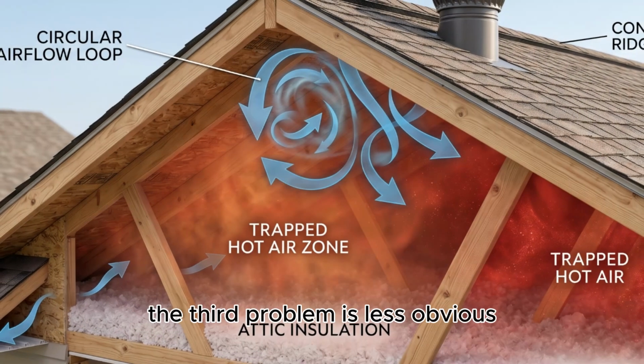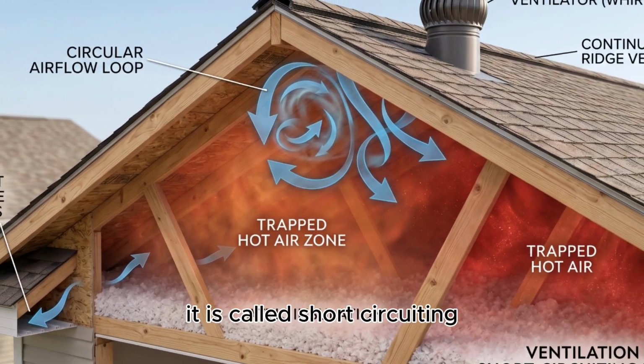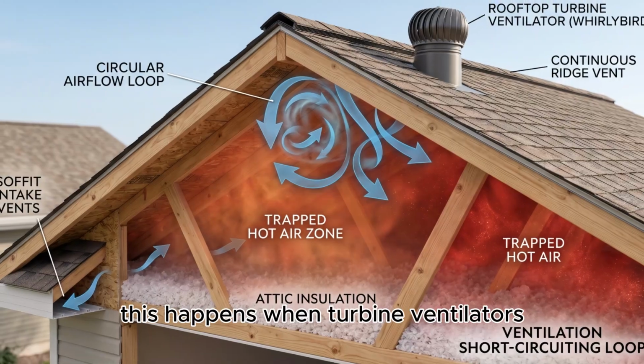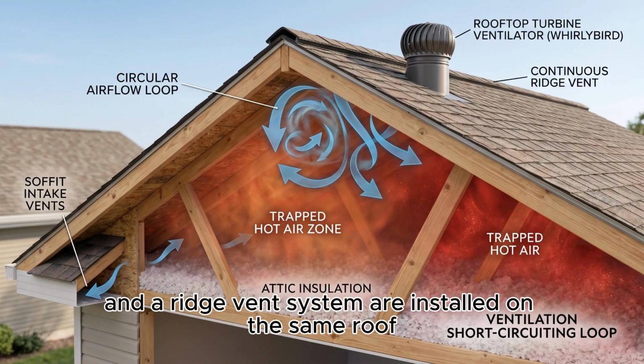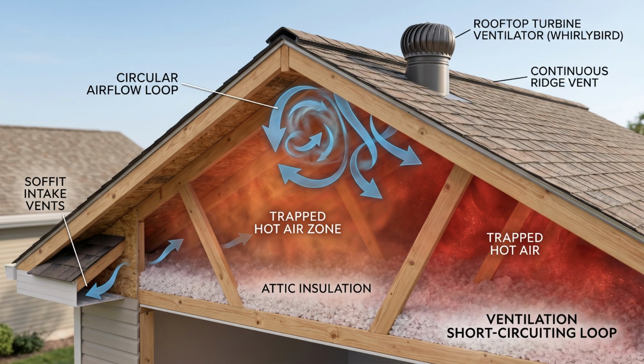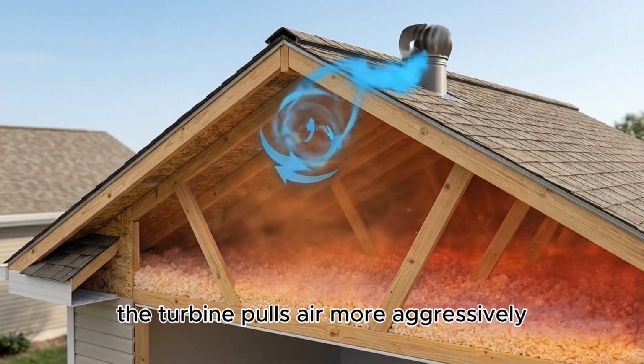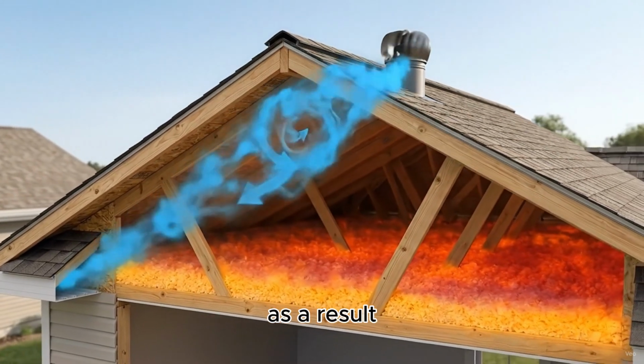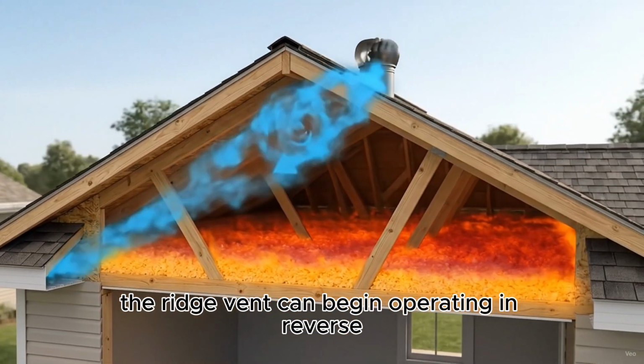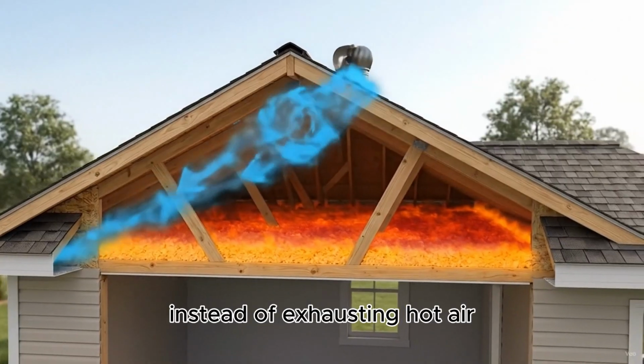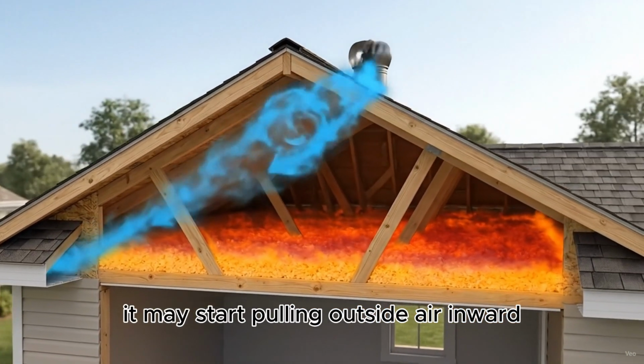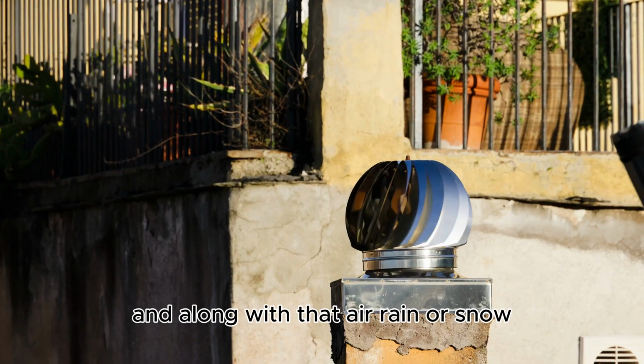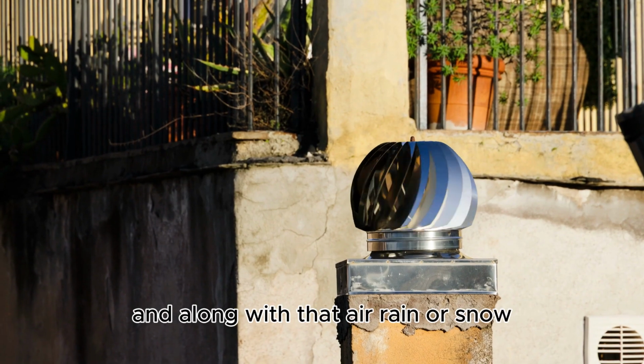The third problem is less obvious. It is called short-circuiting. This happens when turbine ventilators and a ridge vent system are installed on the same roof. The turbine pulls air more aggressively. As a result, the ridge vent can begin operating in reverse. Instead of exhausting hot air, it may start pulling outside air inward. And along with that air, rain or snow.